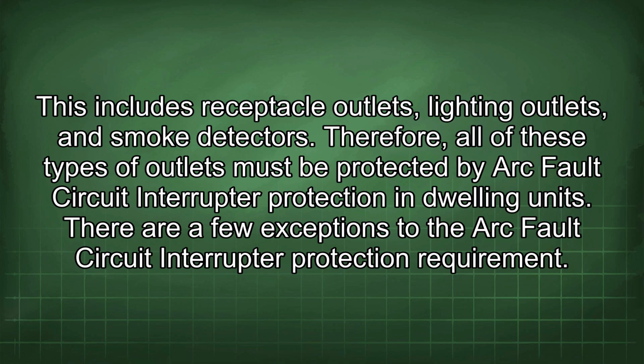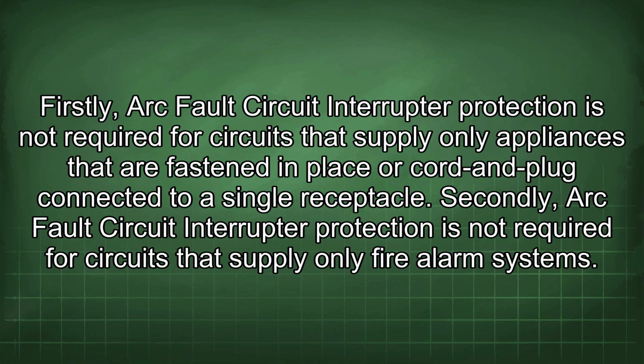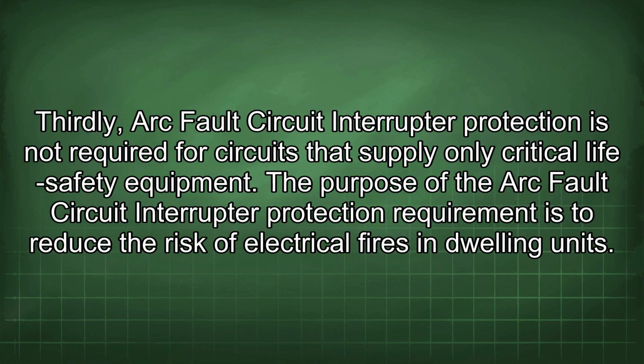There are a few exceptions to the arc fault circuit interrupter protection requirement. Firstly, arc fault circuit interrupter protection is not required for circuits that supply only appliances that are fastened in place or cord and plug connected to a single receptacle. Secondly, it is not required for circuits that supply only fire alarm systems. Thirdly, it is not required for circuits that supply only critical life safety equipment.